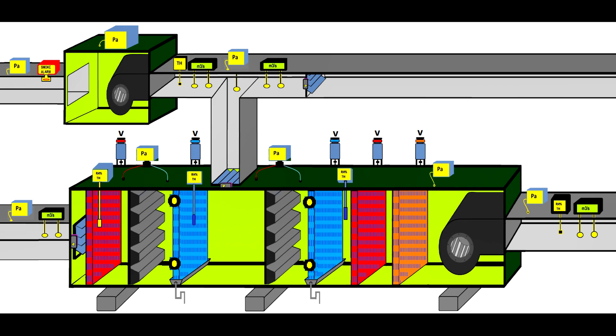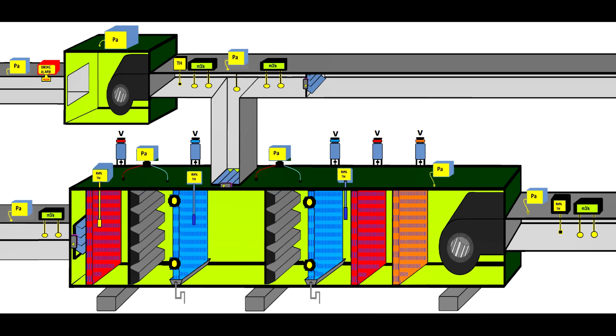This type of unit again is the one which recirculates the air. Like you'll see in this picture, on the left hand side on the top, you have the extractor fan, and you see there's a duct which links the extractor's fan duct to the AHU. And that shows you recirculate part of the air. You see three dampers on the duct that allows you to control the quantity of air that is exhausted, recirculated, or the quantity of fresh air that you want to bring inside the building. The fresh air has heat exchangers, and also after the mixing chamber you will meet the recirculated air. And I'll explain to you in very detail how this works in another video.